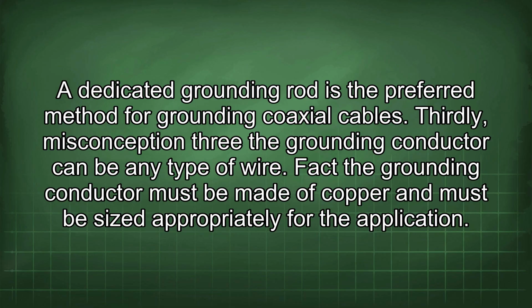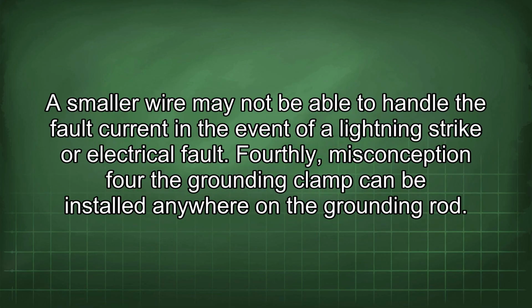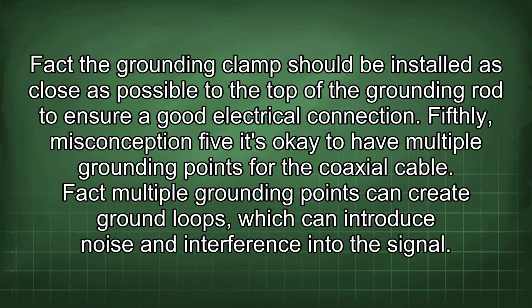Thirdly, misconception 3: the grounding conductor can be any type of wire. Fact: the grounding conductor must be made of copper and must be sized appropriately for the application. A smaller wire may not be able to handle the fault current in the event of a lightning strike or electrical fault. Fourthly, misconception 4: the grounding clamp can be installed anywhere on the grounding rod. Fact: the grounding clamp should be installed as close as possible to the top of the grounding rod to ensure a good electrical connection.